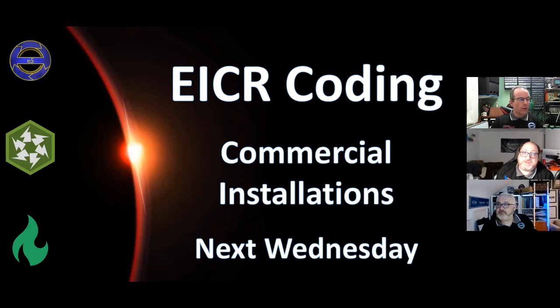Another one from Steve. If you see a C2 on the DNO side, can you still call the EICR satisfactory? So if it's outside, NICEIC told me you can't code DNO side, you can only make a note of it. Well, then tell the NICEIC to put it in writing and be prepared to stand next to you in the dock when the judge is questioning you, because ignorance isn't the defence. That really boils my blood. No. If it's a C2, it's a failure, period. Issue a danger notification, ring the DNO, discharge a duty of care, tell them someone's going to get hurt, put it in writing. The NICEIC guy on the end of a phone isn't the inspector. He doesn't have the duty of care under all the various legislation on him. You do. So, no. Sorry, NICEIC, I'll have a word with John O'Neill when I next see him about that.